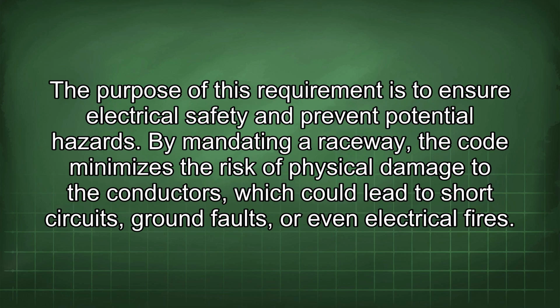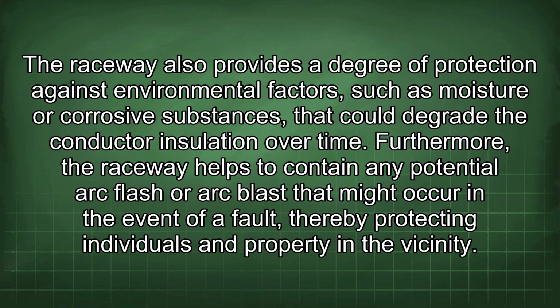The purpose of this requirement is to ensure electrical safety and prevent potential hazards. By mandating a raceway, the code minimizes the risk of physical damage to the conductors, which could lead to short circuits, ground faults, or even electrical fires. The raceway also provides a degree of protection against environmental factors, such as moisture or corrosive substances, that could degrade the conductor insulation over time. Furthermore, the raceway helps to contain any potential arc flash or arc blast that might occur in the event of a fault, thereby protecting individuals and property in the vicinity.